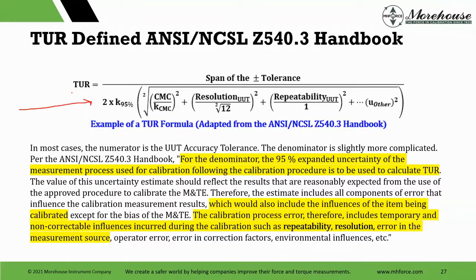And it says for the denominator, the 95% expanded uncertainty of the measurement process used for calibration following the calibration procedure is used to calculate TUR. And it says right here, what does it include? Item being calibrated, except for bias of the MTE. The calibration process error includes temporary and non-correctable influences incurred during the calibration, such as repeatability, resolution error in the measurement source, operator error, error in correction factors, and environmental influences.